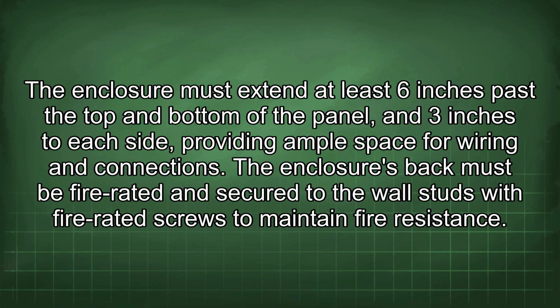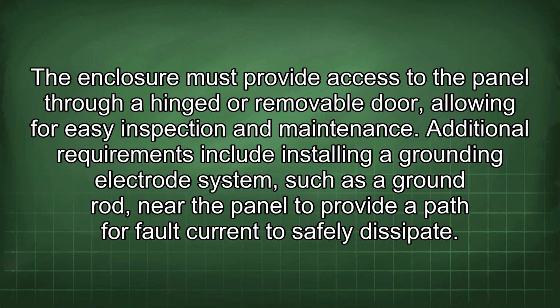The enclosure must extend at least 6 inches past the top and bottom of the panel and 3 inches to each side, providing ample space for wiring and connections. The enclosure's back must be fire-rated and secured to the wall studs with fire-rated screws to maintain fire resistance. The enclosure must provide access to the panel through a hinged or removable door, allowing for easy inspection and maintenance.